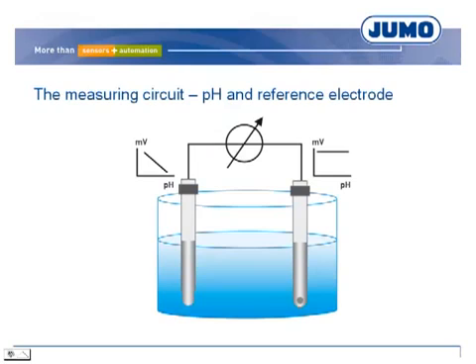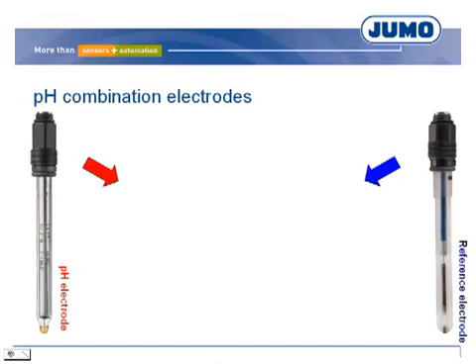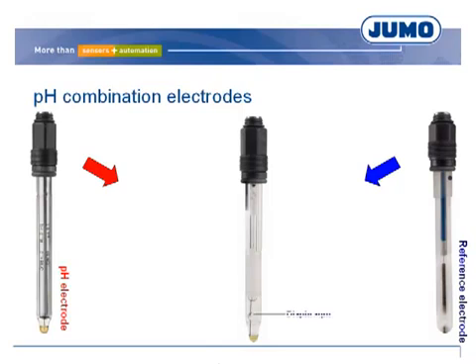The picture shows the measuring circuit principle with pH and reference electrode. pH and reference electrodes come together in so-called pH combination electrodes. Constructionally, the reference electrode is built around the pH electrode. The pH combination electrode contains the components of the pH electrode — membrane glass, internal electrolyte, and internal conductive element. It also contains the components of the reference electrode: diaphragm, reference electrolyte, and reference conductive system.